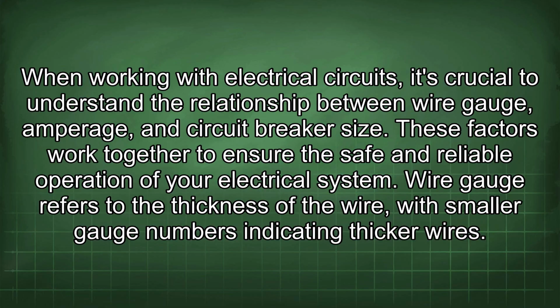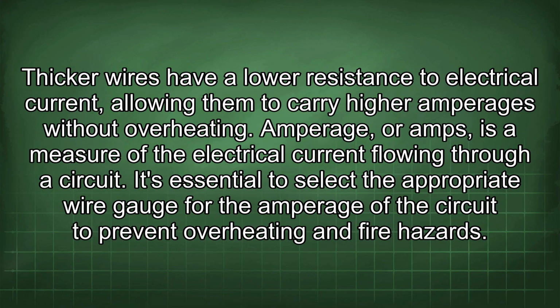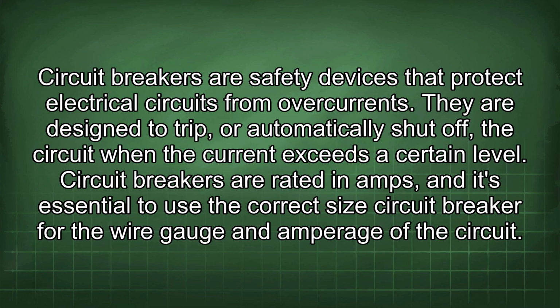Wire gauge refers to the thickness of the wire, with smaller gauge numbers indicating thicker wires. Thicker wires have a lower resistance to electrical current, allowing them to carry higher amperages without overheating. Amperage, or amps, is a measure of the electrical current flowing through a circuit. It's essential to select the appropriate wire gauge for the amperage of the circuit to prevent overheating and fire hazards. Circuit breakers are safety devices that protect electrical circuits from overcurrents. They are designed to trip, or automatically shut off, the circuit when the current exceeds a certain level. Circuit breakers are rated in amps, and it's essential to use the correct size circuit breaker for the wire gauge and amperage of the circuit.